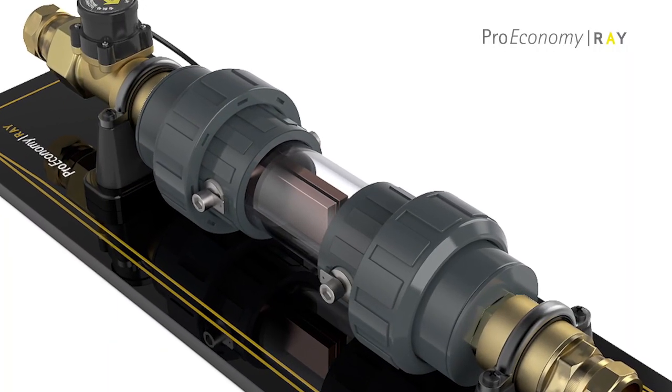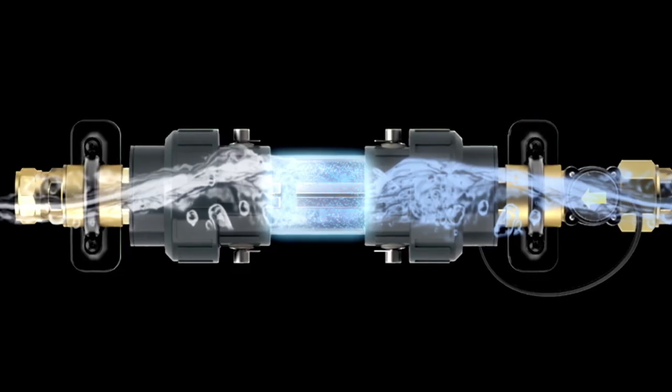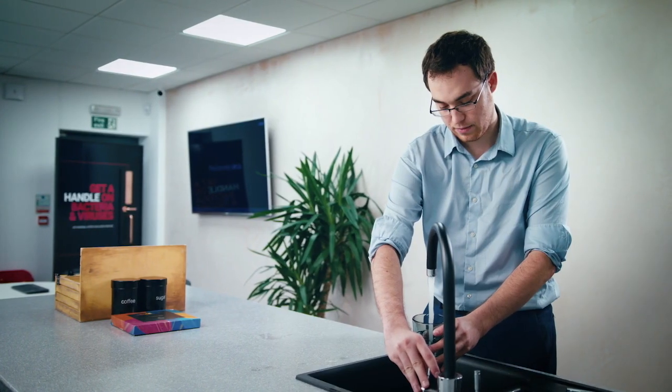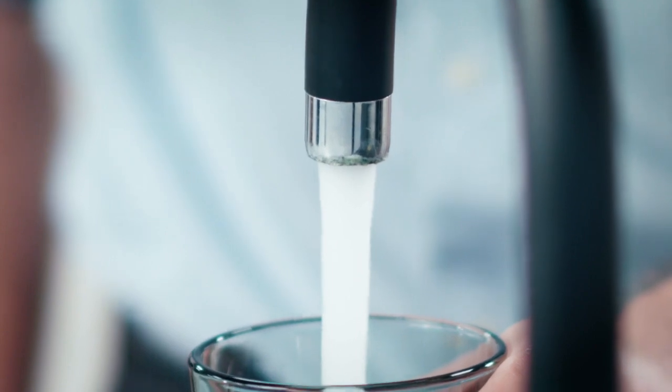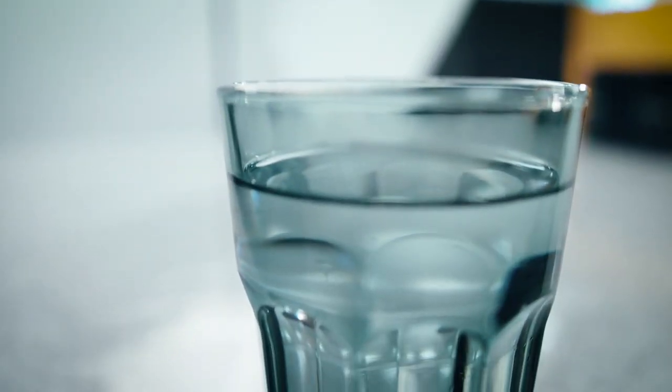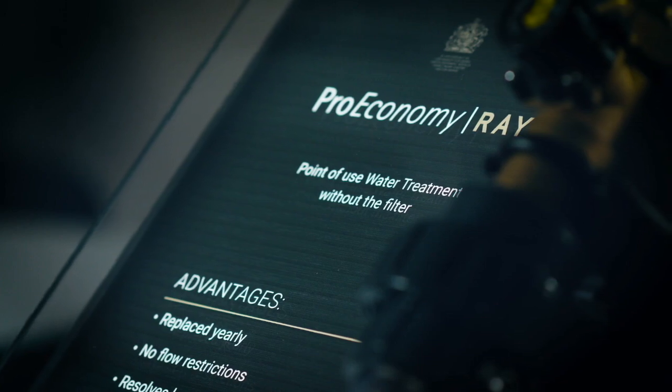The RAY system is a copper and silver ionization system — an inline system that holds solid copper and solid silver electrodes. An electrical current is passed across the bars which enables positively charged copper and silver ions to be released into the water to kill bacteria. Copper and silver ionization can kill biofilm, it can kill legionella and other bacteria within water systems. It is proven to be the longest-lasting modality and I don't believe there's anything on the market capable of treating such small levels of water in such a safe way.